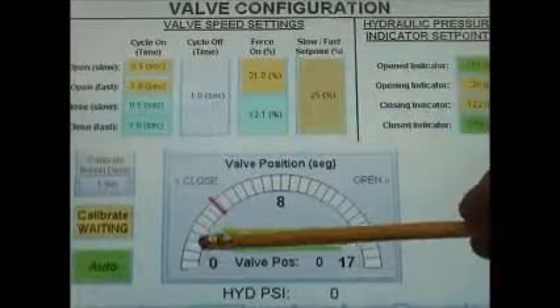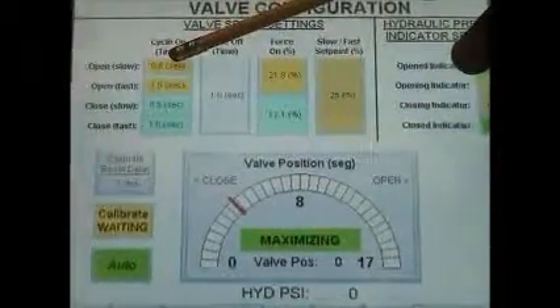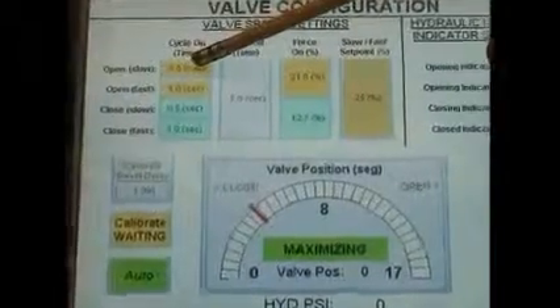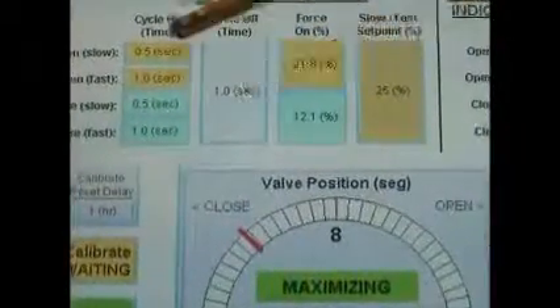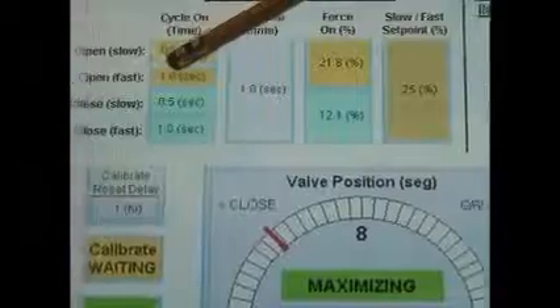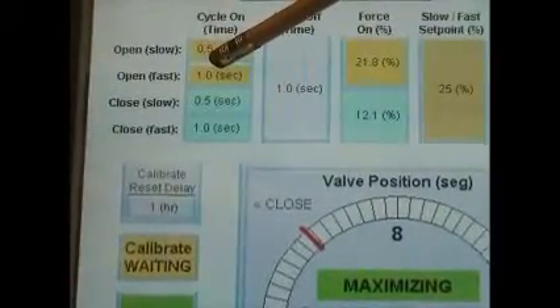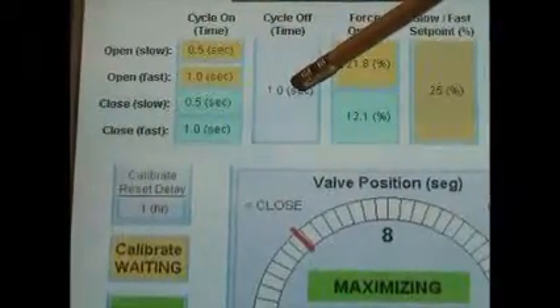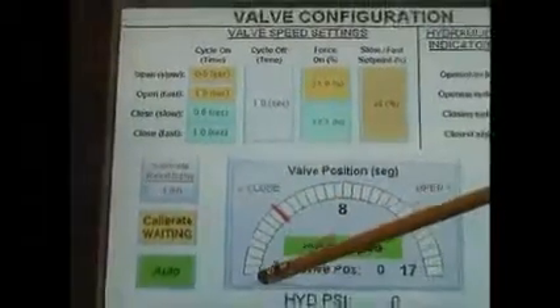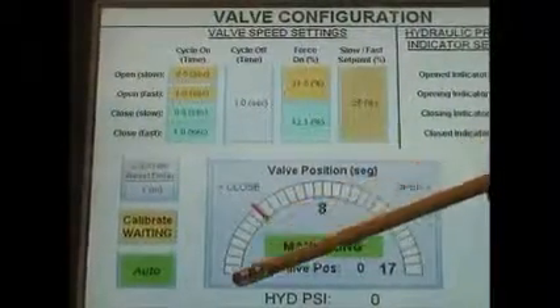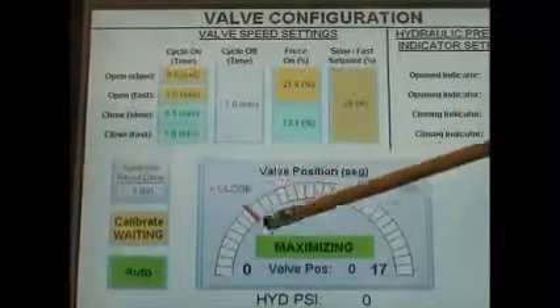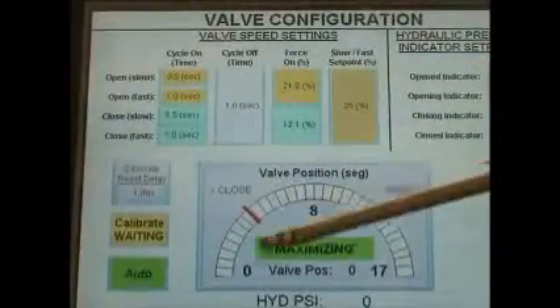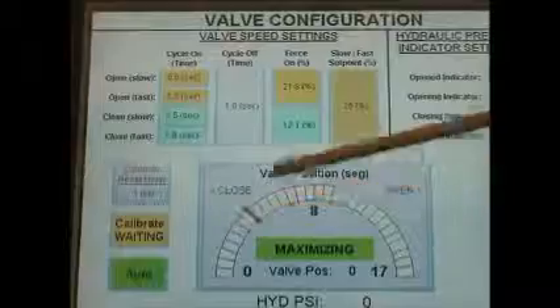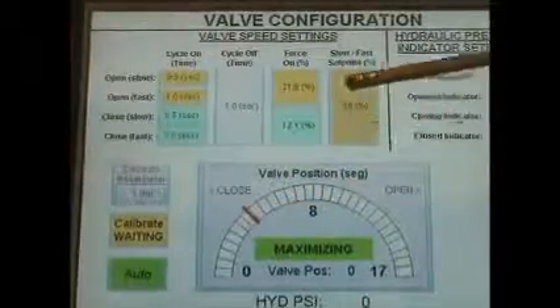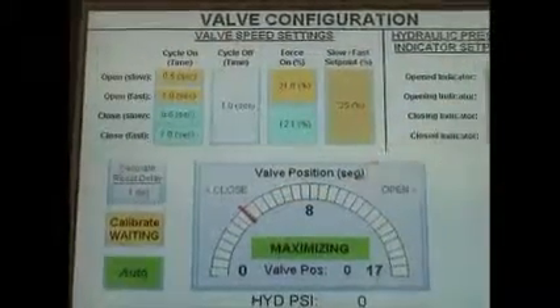Now what the valve is going to do is, instead of opening for half a second and stopping for 1 second, it's going to open for a 1 second period and then also stop for 1 second, as long as the valve is between 0 and whatever your 2-speed set point is. So once we change the 2-speed set point, the valve needs to recalibrate itself.